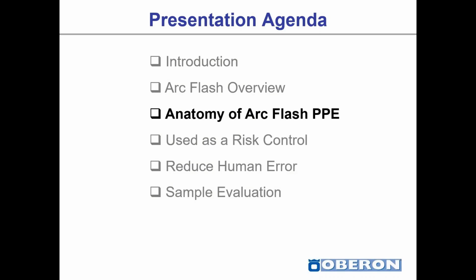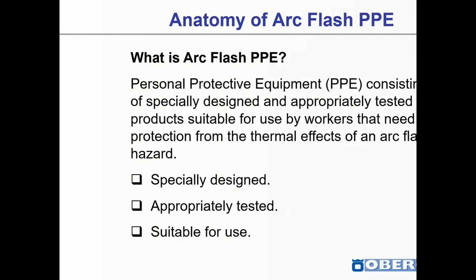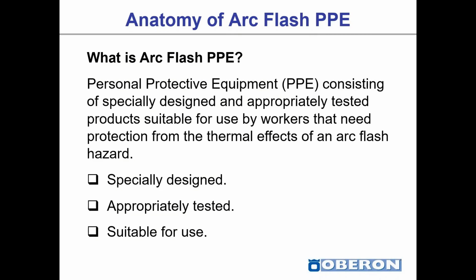Just to keep it focused here on the presentation, we're going to talk more about the anatomy of Arc Flash PPE, how we're using it as a risk control, and then more of the leading edge information and subject matter, which is how do we reduce human error. By reducing human error, we can certainly reduce the likelihood of an arc flash occurring. So in terms of the anatomy of Arc Flash PPE, it's personal protective equipment consisting of specially designed and appropriately tested products suitable for use by workers that need protection from the thermal effects of an arc flash hazard. Specially designed, appropriately tested, and suitable for use are the 3 key points.